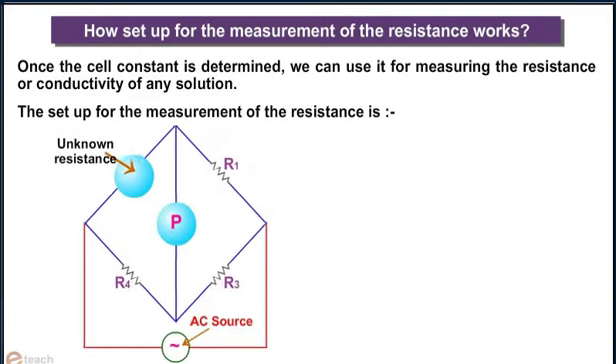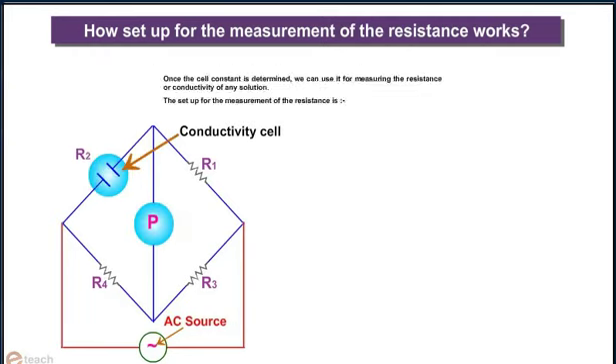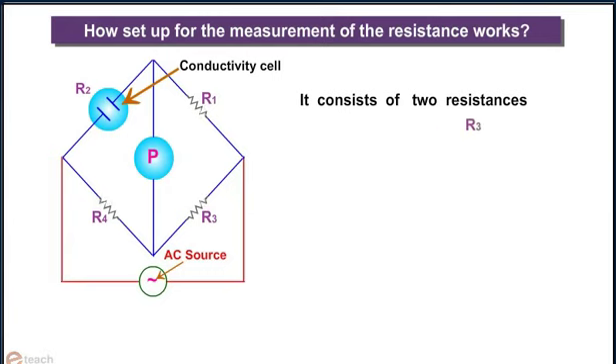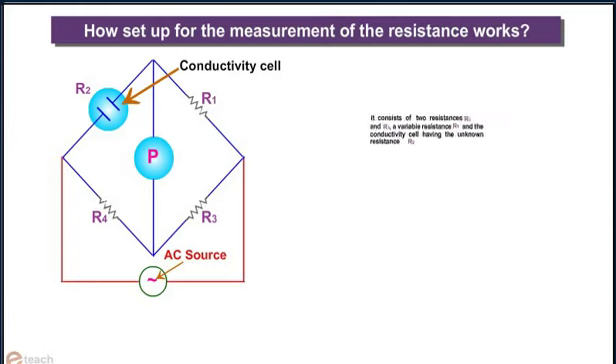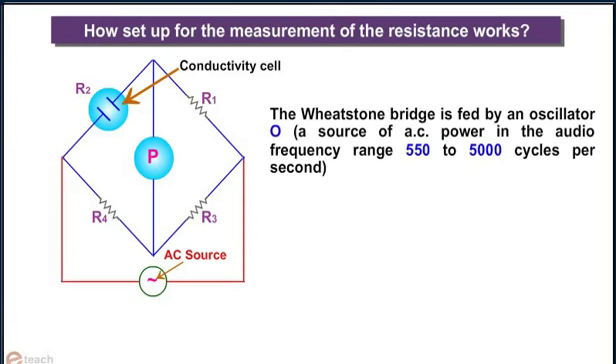The setup for the measurement of resistance is shown in the given diagram, which is a setup for the Wheatstone bridge circuit. It consists of two resistances R3 and R4, a variable resistance R1, and the conductivity cell having the unknown resistance R2. The Wheatstone bridge is fed by an oscillator O, which is a source of AC power in the audio frequency range of 550 to 5000 cycles per second.